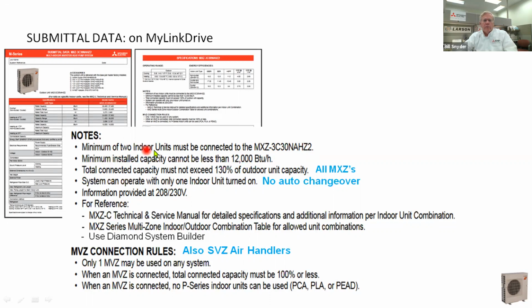You have to have a minimum of 2 indoor heads on all MXZ units. So those 2 indoor heads could be 12,000 BTUs. That's fine. Total connected capacity cannot exceed 130%. What that's saying is if you sell a 4-ton unit and you put 5 1-ton heads on it, that's 60,000 BTUs of heads. That's acceptable. It will work, but you're not going to get 60,000 BTUs out of it. You're only going to get what the outdoor unit can do, which is 48,000.